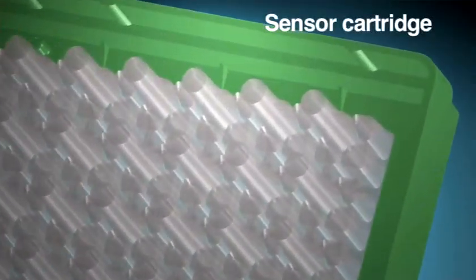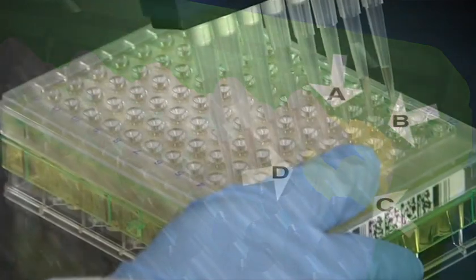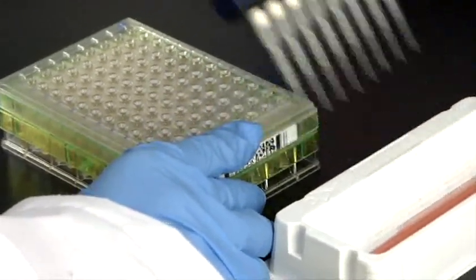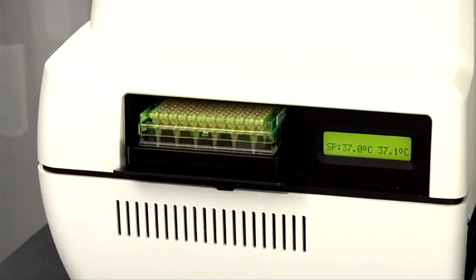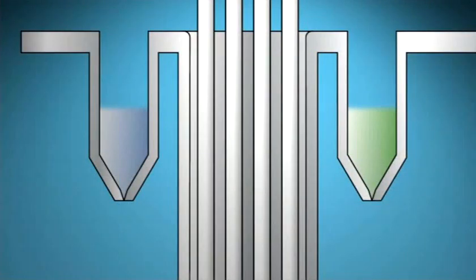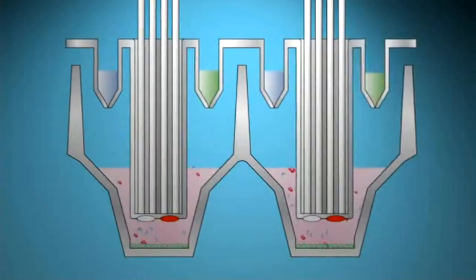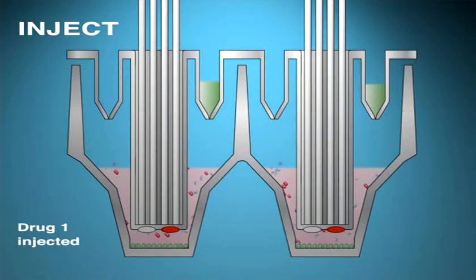Surrounding each of the sensor sleeves are four drug injection ports. Loading these drug ports is easy. Simply pipette the drugs into the delivery ports of the sensor cartridge using the drug delivery guide and insert it into the XF Analyzer to run your assay. The dispensed drugs are held in the injection ports by capillary action. The XF Analyzer then pneumatically injects each port at time points specified by your experimental protocol.